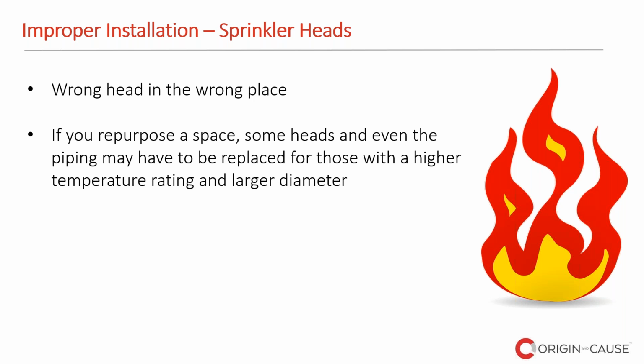Now, the wrong head in the wrong place. Again, as I was saying, when you repurpose a space, you always have to rerun the calculations and rerun the occupancy calculations, occupancy drawings, the size of the sprinkler head, the size of the sprinkler system, location of the heads, and reinstall the appropriate heads.